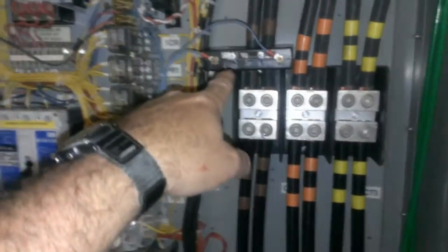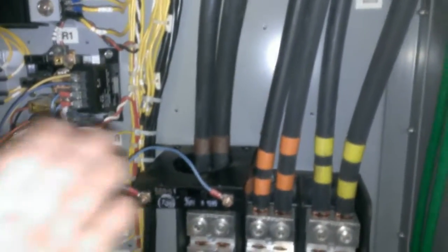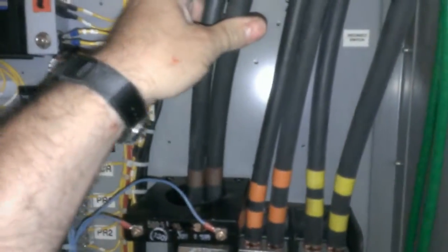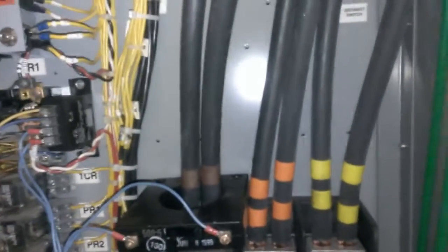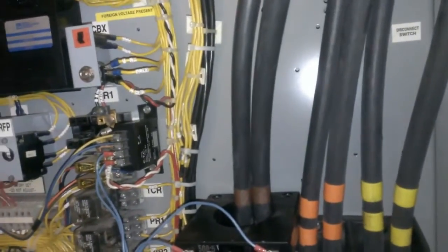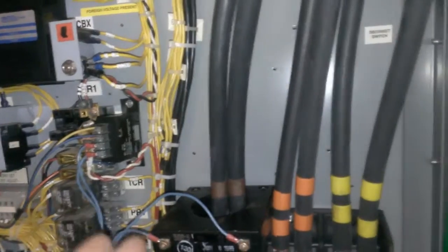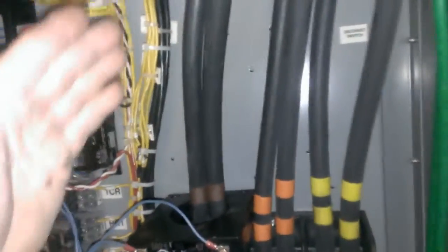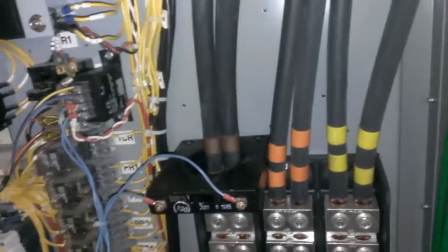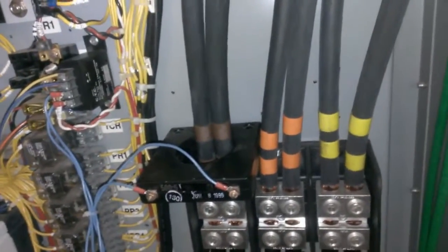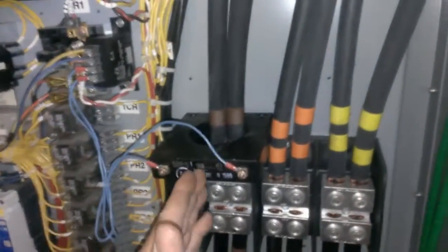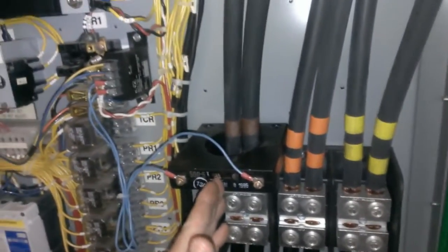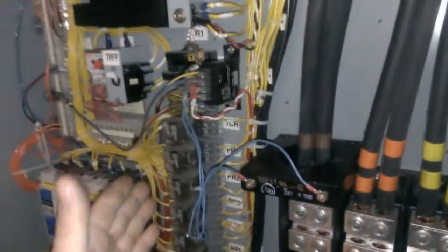So, it could, this thing might, it's probably not going to read accurately being used on the motor side of the VFD. So basically, this is on the line power side now, feeding before it goes to the chiller, the VFD. So this is going to read actually like what the current is that you're demanding from the utility company. And that's what we want to see on the screen of the EMS. So I put this on here, move the converter over to here. It's reading accurately, just like when I put my clamp-on meter there.